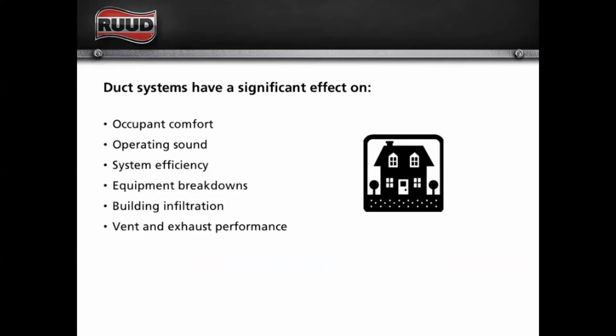The duct system and the way those ducts are run and laid out has a significant effect on a lot of things, right? It affects many things, including the comfort and operating sound. Okay, so comfort wise, we don't want our registers to blow directly on your customer who maybe is sitting in their favorite chair watching TV, unless that's what they want. But a lot of times that's great in the cooling cycle, but it's not so great in heating, right? That creates a draft. The air is warmer than ambient, but it might feel cold against that person's skin. So that can affect comfort.